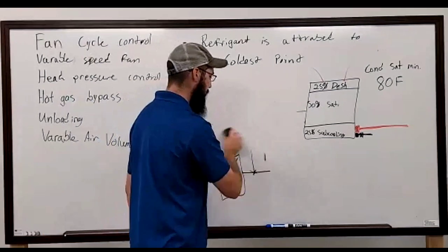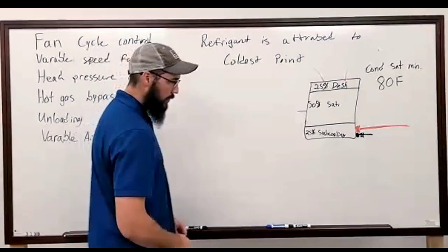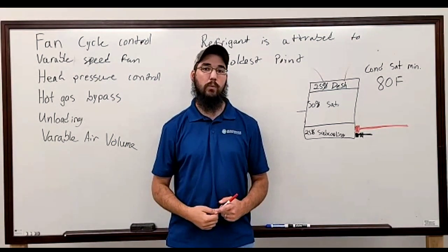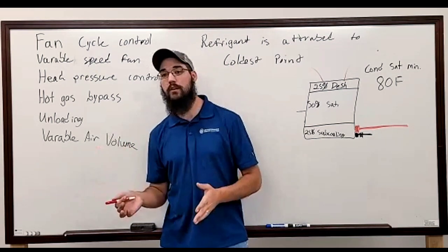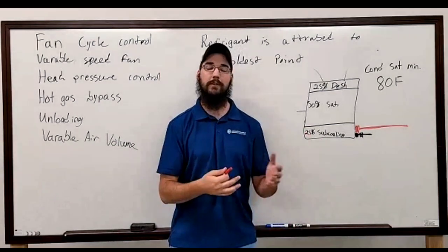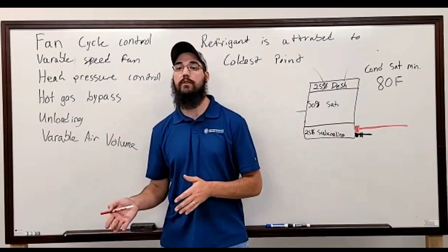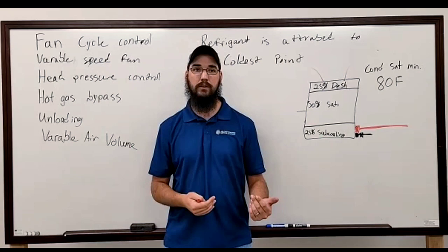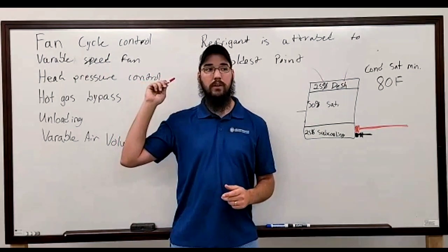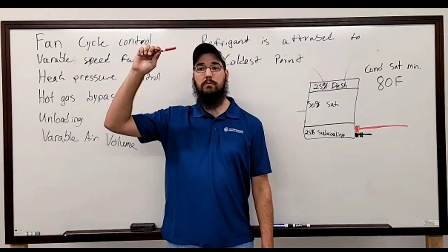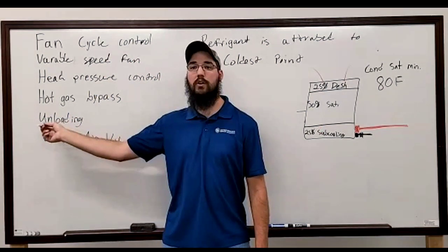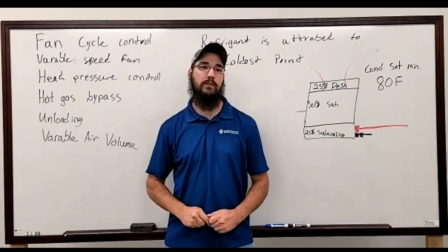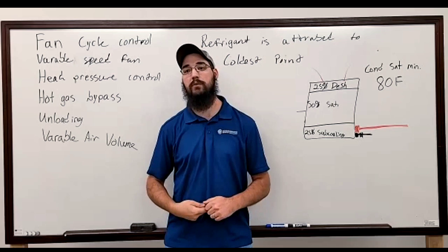Unloading goes back to the variable speed compressor conversation. So we're not using compressor unloading for head pressure control. Whether it's an electronic unloader, an electromechanical unloader, or a straight mechanical unloader, either way, the unloader's function is to help the compressor control load, not head pressure. And where a variable speed compressor may actually be limited by conditions, most of the time your hard load and unload compressors won't. There's not that much logic there on those. So they will push themselves to the point of tripping on safeties, where a lot of your variable speeds probably won't. They'll limit out before they ever get there.